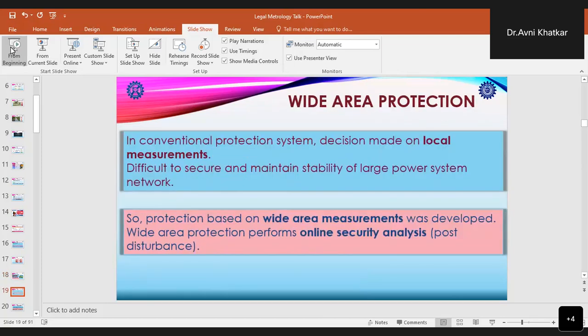When we talk about wide area management, wide area protection also comes into the picture. Initially, in conventional protection systems, all the decisions were made on local measurements. Because of these local measurements, it was very difficult to secure and to maintain the stability of large power system networks. So now, wide area measurement based protection was developed so that we can have a wide area protection system which can perform online security analysis, and we can also have a post-disturbance analysis of the complete system.